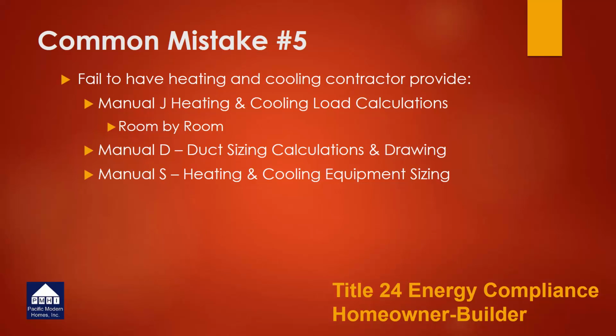The next most common mistake I encounter is failure to have the heating and cooling contractor provide Manual J heating and cooling load calculations. These have to be done on a room-by-room basis, along with Manual D duct sizing calculations and Manual S heating and cooling equipment sizing, to the building department for plan check and review. Now, many jurisdictions are now enforcing this. This requirement has been a CalGreen requirement for the last 6 years. Building departments are just getting to the point where they're requiring it.